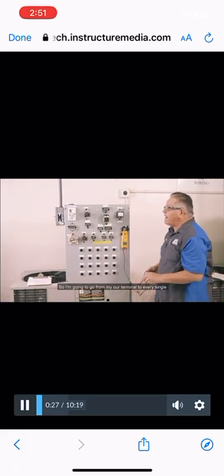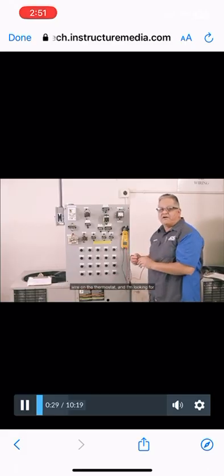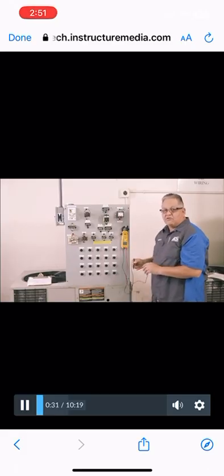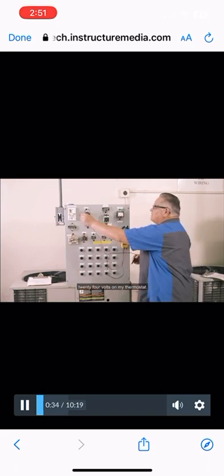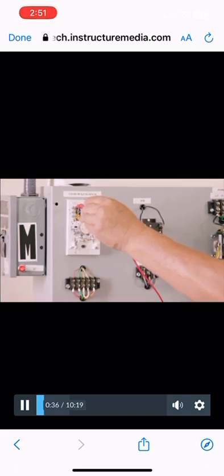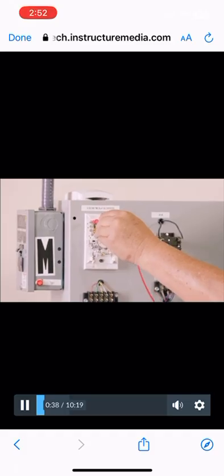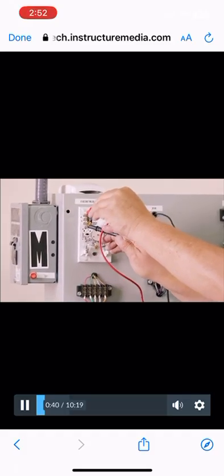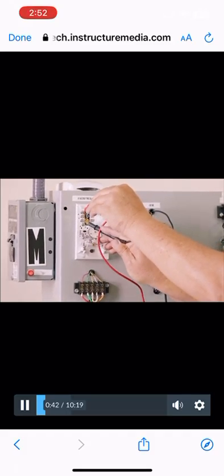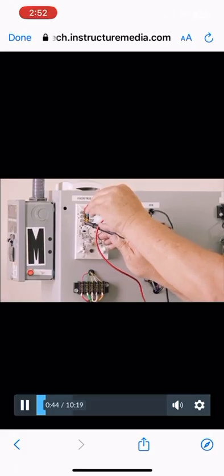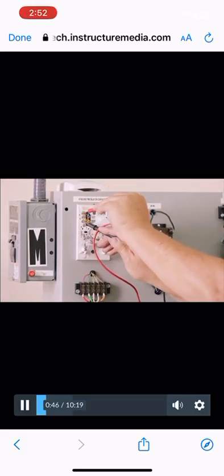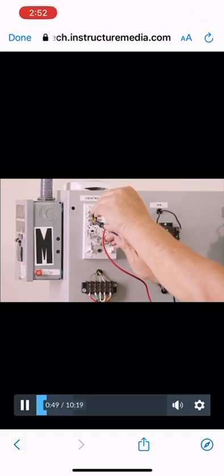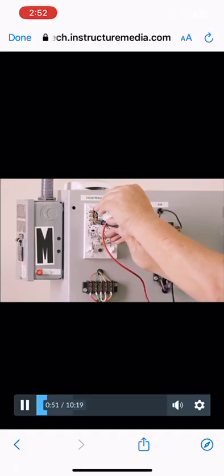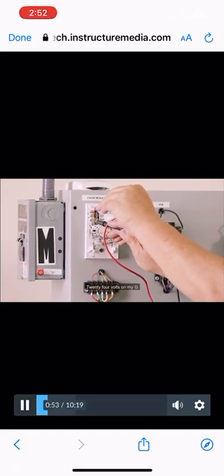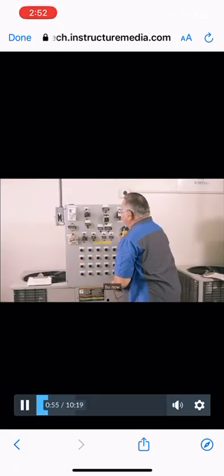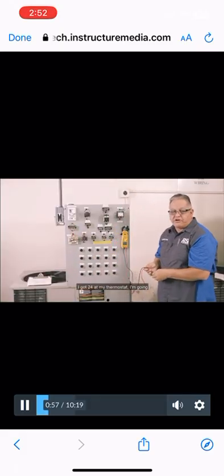So I'm going to go from my R terminal to every single wire on the thermostat, and I'm looking for 24 volts on my thermostat. So I'm going to go from my R terminal to my G, and I'm reading 24 volts on my G. So now I got 24 at my thermostat.